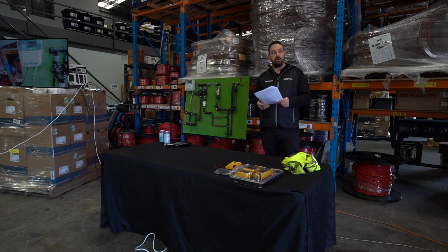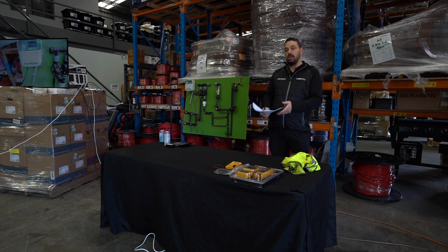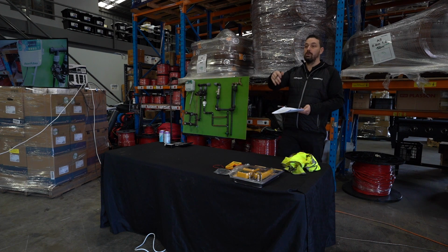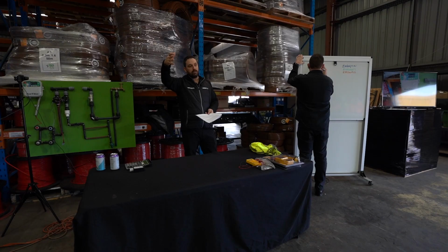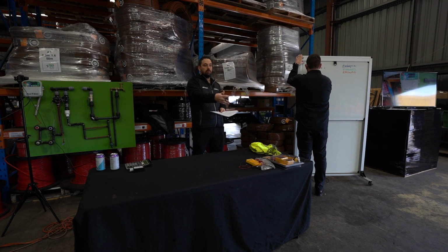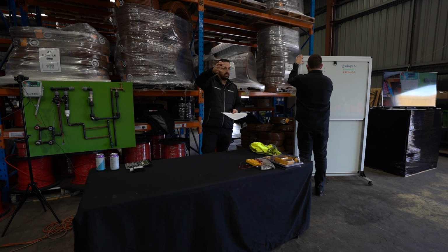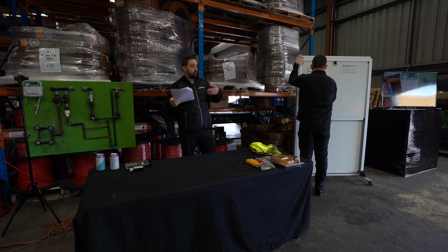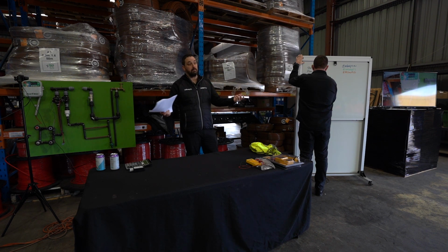If you were doing that on a commercial side of things, you might have a backflow given to you, or if it's a new build or a new development. This happens a lot with the APG side of things for us as well. A new subdivision's going in or a new reserve's going in. We know that they've given us a 40 or a 50 mil water meter there. I'll say, okay, can I come off that and do a flow test from there, and we'll try and do some tests. That might be a case of just concocting a bit of 50 mil PVC or some flexible hoses to come out of that water meter or a backflow, and then we can do the same thing. Tap, outlet, either way it's a water source for us to be able to do it. Even if it's a pump, we can do the same sort of thing.